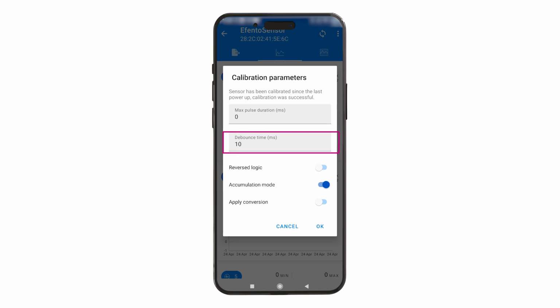Debounce time. This parameter helps prevent incorrect pulse counting in the event of electrical interference caused by factors such as machines located near the pulse counter installation, excessively long wires connecting the pulse-generating element to the sensor, or the commonly known phenomenon of contact bounce. Setting the debounce time enables the blocking of pulse counting from the moment the input state changes, for the duration specified in this parameter. Reverse logic. Enabling this option will change the pulse counting from rising edge to falling edge.